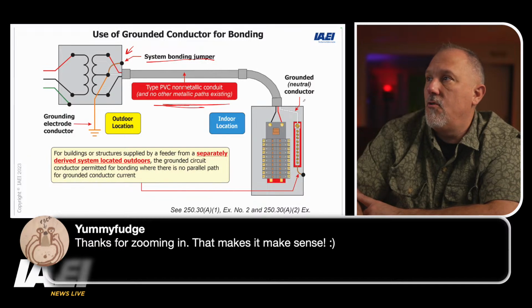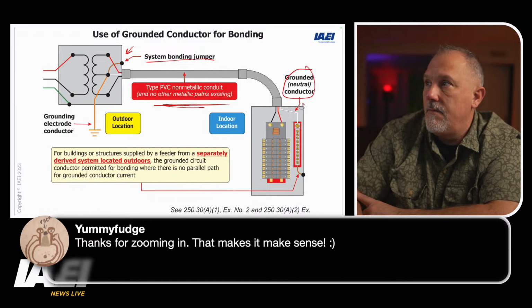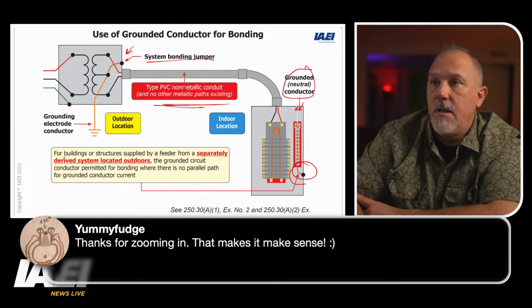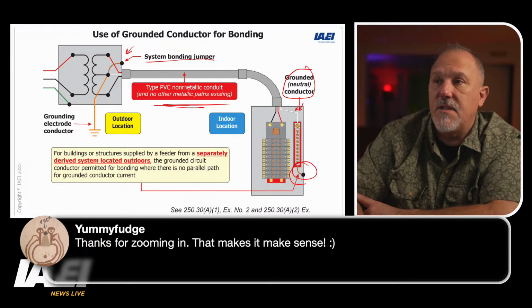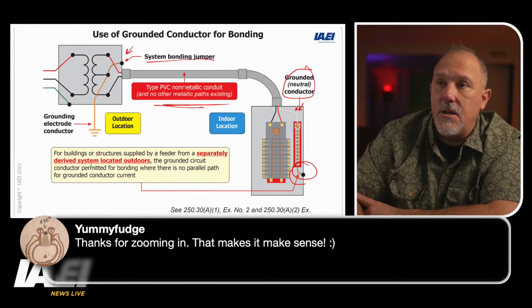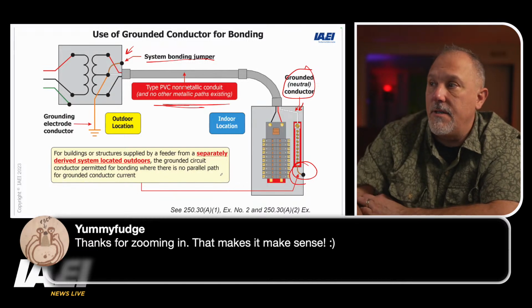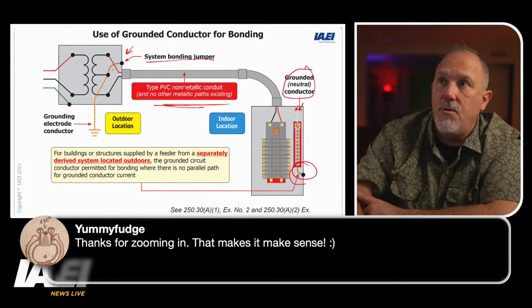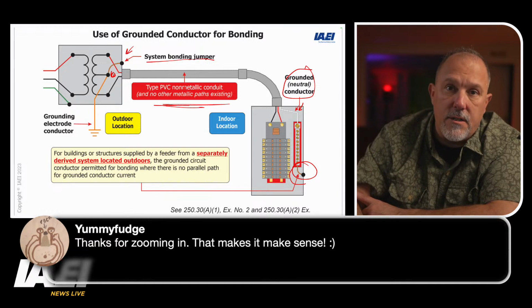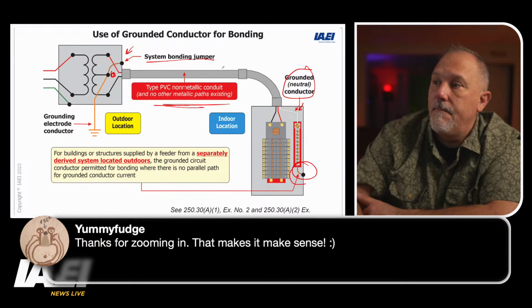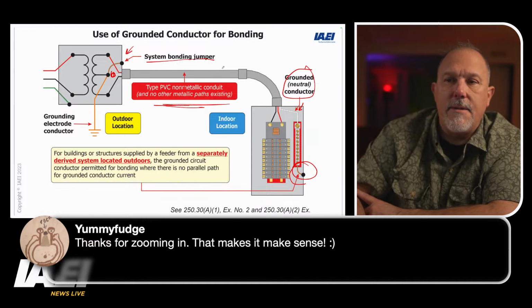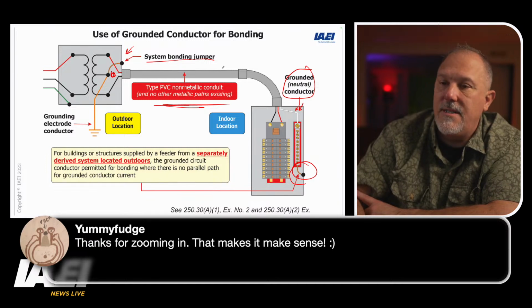You have your grounded neutral conductor, and then we bond here to this enclosure. For buildings or structures supplied by a feeder from a separately derived system located outdoors, the grounded circuit conductor is permitted for bonding where there's no parallel path for grounded conductor current. So this is when you are using the grounded conductor, which is derived right here at the source of that separately derived system. That's 250.30(A)(1) exception number 2. Isn't that beautiful? Now I can erase all ink on the slide.